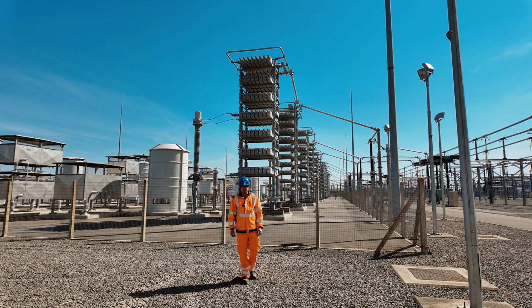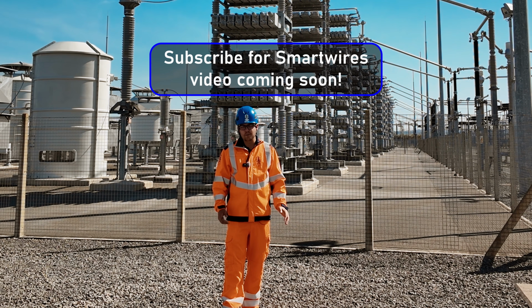There's a few ways to influence where power goes on the grid, and I've done another video on phase shifting transformers, or quad boosters as we call them, and you can take a look at that up there. You can use power electronics as well to influence where power goes on the grid, a bit like the HVDC technology that's just over there. But the simplest way to influence power flows is to change the impedance of the line.